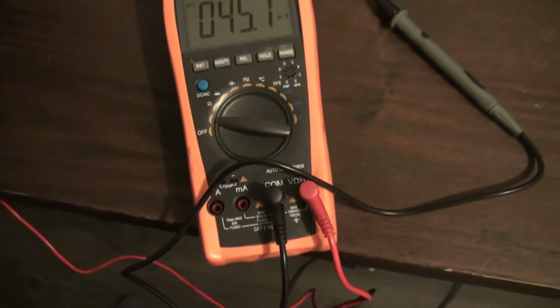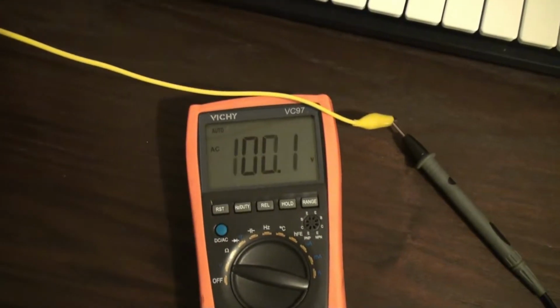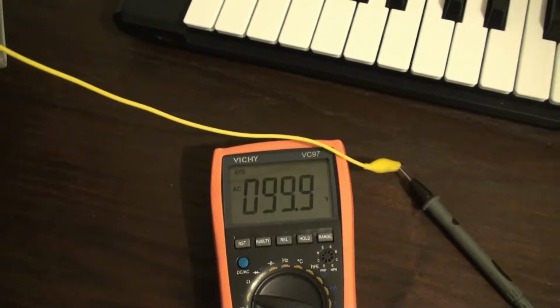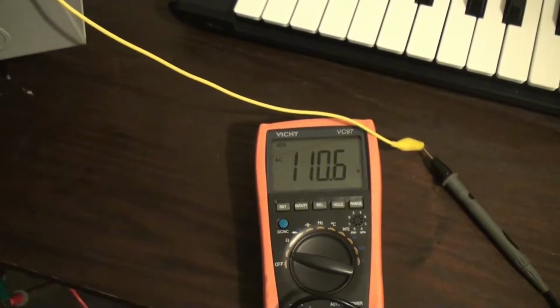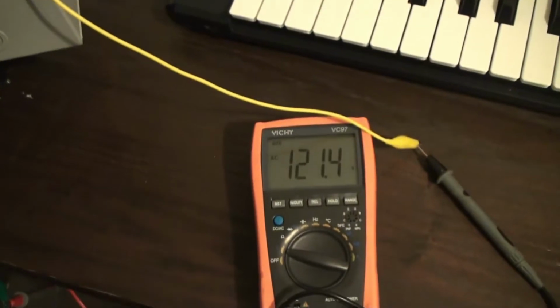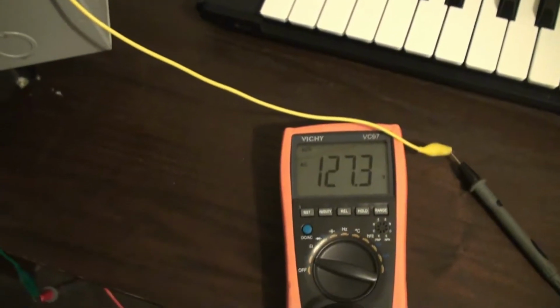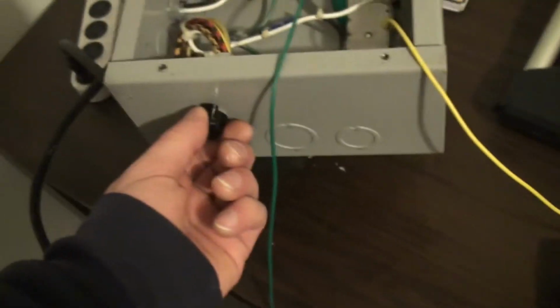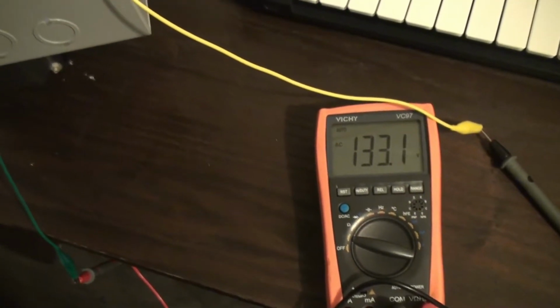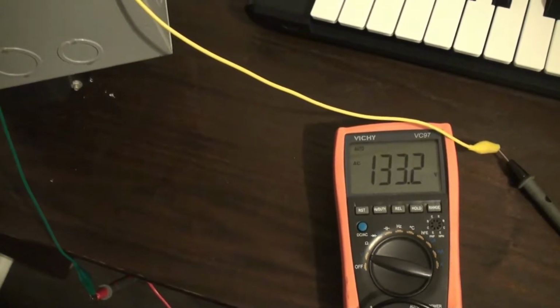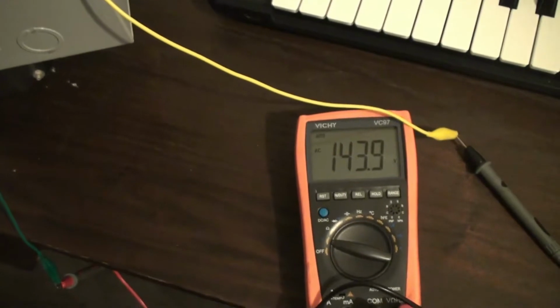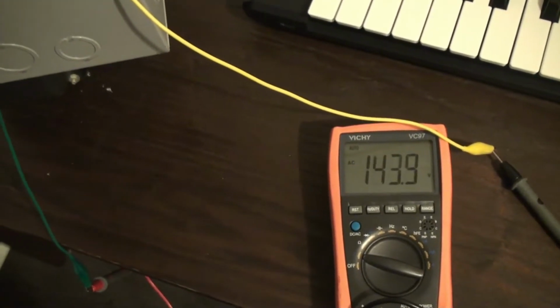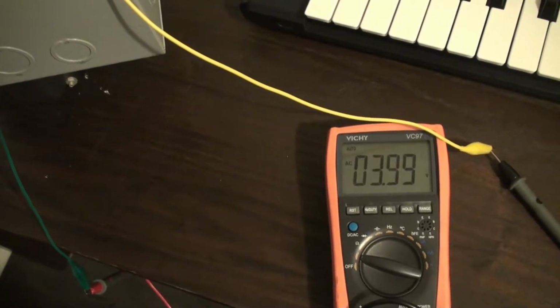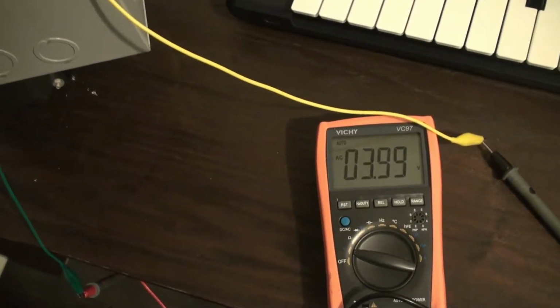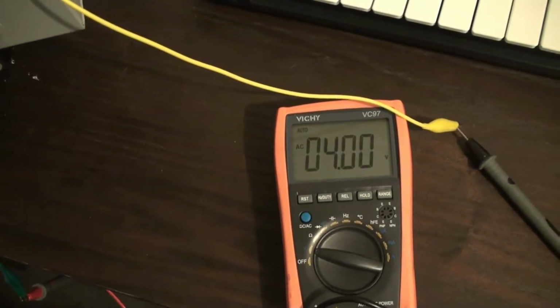So this tap, we've got, let's see, DC volt, AC, 100 volts. 100 volts. Next tap, 110. 120. That's probably supposed to be 130. The last one, well, maybe not. Could be wrong. Last one I believe was 127. This is 133. Last tap is 144. And the last one here seems to be reading 4 volts.